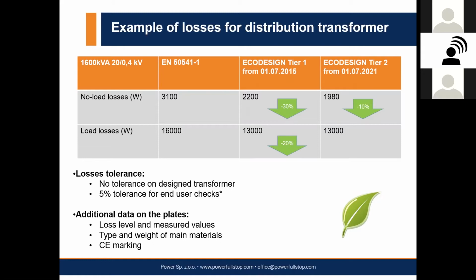And just to confirm this second step of the regulation, on the 18th of November 2019 there was a new regulation modifying the eco-design Tier 2 stage. This is a very interesting point. Just to remind you shortly, with the first regulation, Tier 1, the losses were reduced by 30% for no-load losses and 20% for load losses. There is no tolerance on the losses, so it must be 0. The only point which is confirmed is a 5% tolerance on the final checks, but it means that if the transformer is checked by a public entity, it's not valid for the private market. So if somebody is telling you that there is a tolerance on eco losses of 5%, this is not true. This is just to permit a small tolerance on the measurement at the final utilization point. So it's not for the private market.